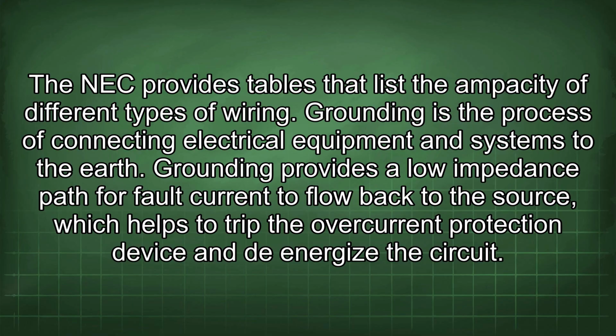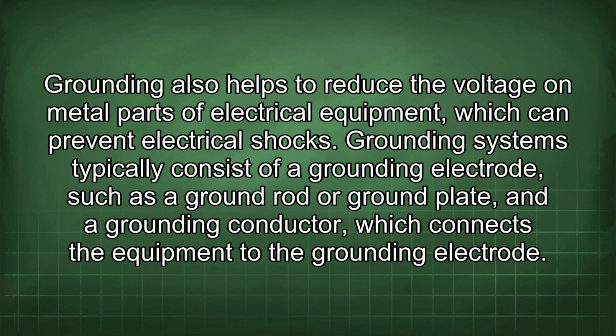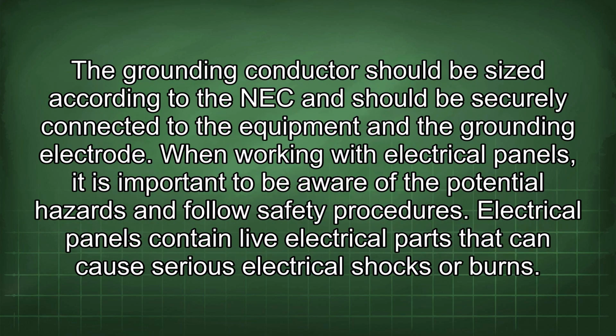Grounding is the process of connecting electrical equipment and systems to the earth. Grounding provides a low impedance path for fault current to flow back to the source, which helps to trip the overcurrent protection device and de-energize the circuit. Grounding also helps to reduce the voltage on metal parts of electrical equipment, which can prevent electrical shocks. Grounding systems typically consist of a grounding electrode, such as a ground rod or ground plate, and a grounding conductor, which connects the equipment to the grounding electrode.